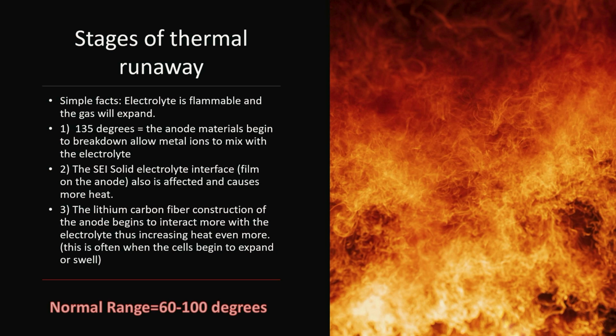Now, stage 1. We talked about simple facts first: the electrolyte, no matter what substance it's made of, is a flammable gas. It's going to involve some technology and science as we go through this. Stage 1 of thermal runaway happens at about 135 degrees Fahrenheit. The anode materials begin to break down and allow metal to mix with the electrolyte. We're going to show you a video, and that metal mixing with the electrolyte becomes dangerous if a full-blown fire were to occur. We'll show you that in a second.